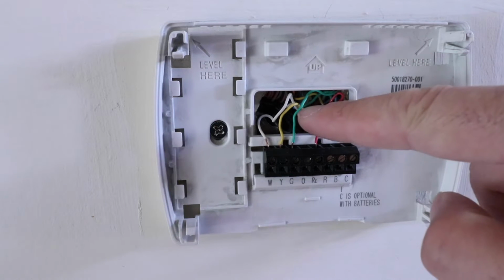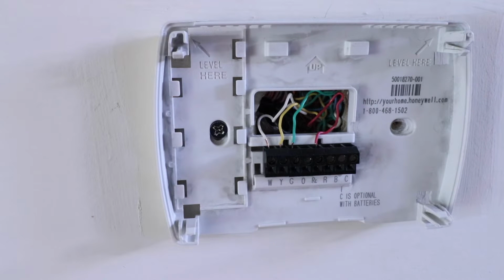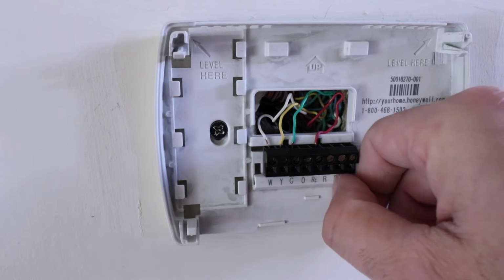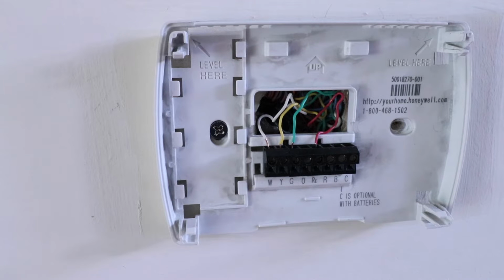Now that's what we're going to focus in on. If you take your G wire, and instead of having independent fan control, you move it over to the C terminal here at the thermostat and the C terminal down at the HVAC system, you can use that G wire as a common wire and your HVAC system is going to work.